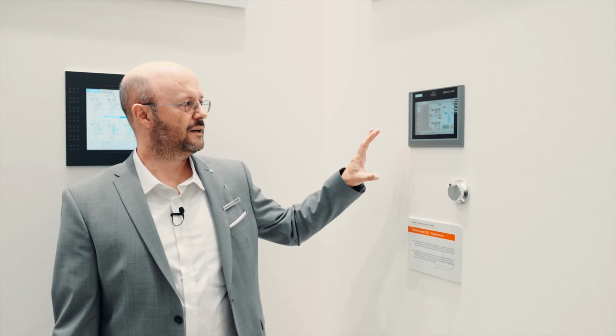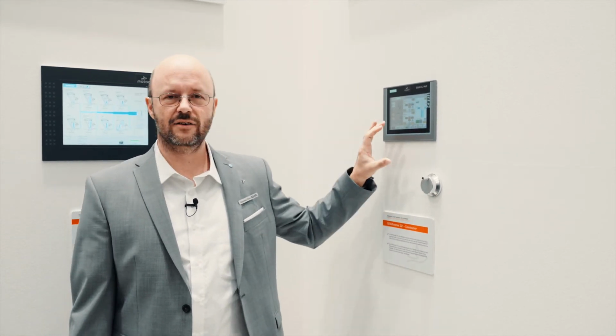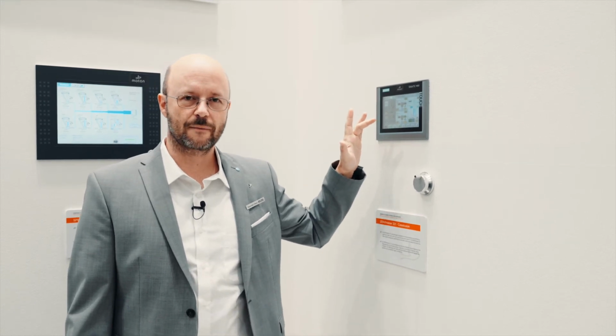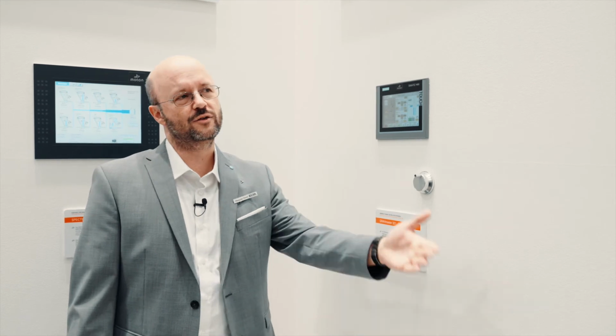And this system runs the extruders, gets information from the machine, puts the outputs to the machine, how fast the extruders should run to reach their throughput, and in other terms goes for the calculation for weight per meter, and then also is able to run a weight per meter control in terms of throughput for the whole extruders. So the setup of the machine is handled here in some kind of recipe. The operator gets information where to put the speeds on, and the system measures the throughput and gives the operator the information and values back, so that he can decide whether the product is now in the range it should be and run for production, and also counting the units.